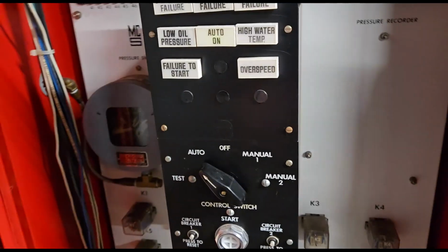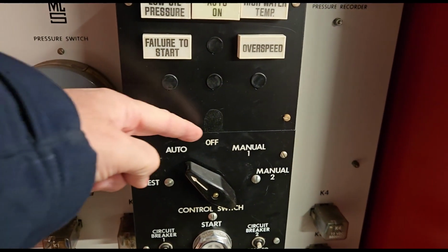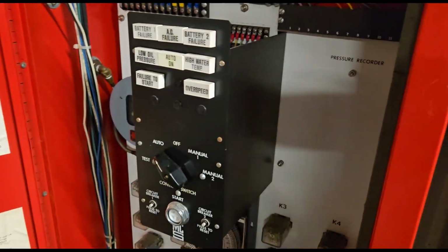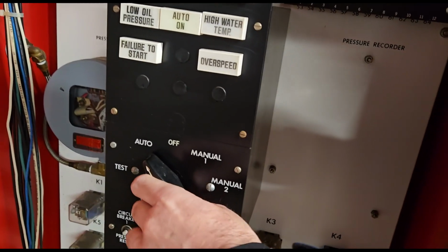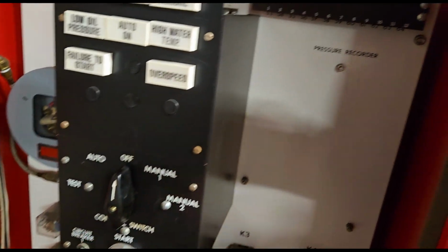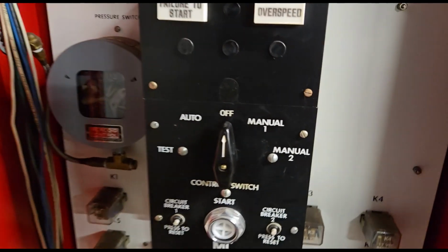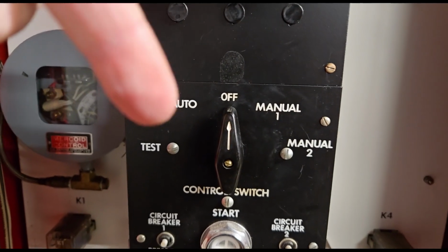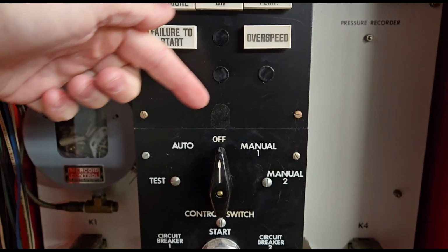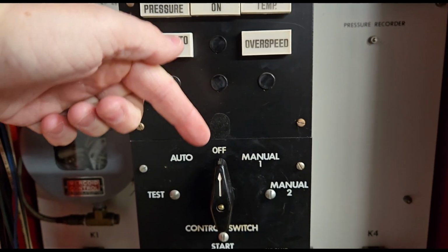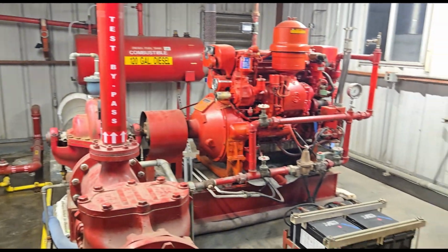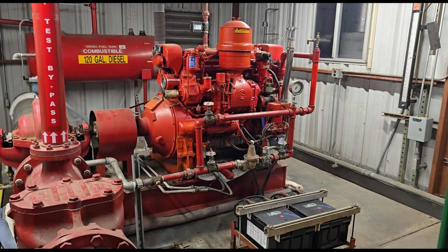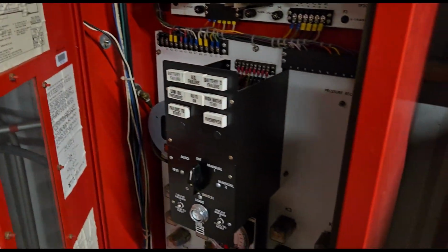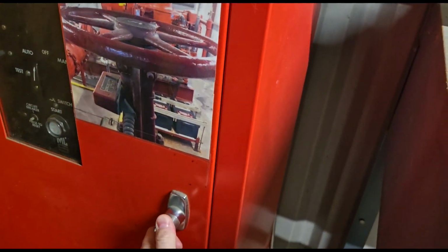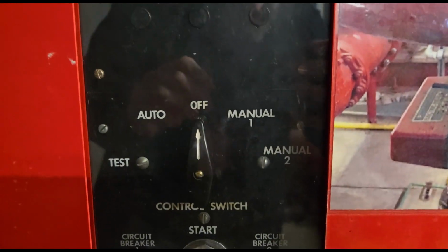So we're going to go ahead and just turn this dial from auto to off. Again, I'm going to stand off to the side, tilt my camera over, and we're just going to go like that to off. So now you see it was first on auto, now it's on off. So now the pump is off. This fire pump will not turn on for our flow testing. So we're just going to close up our door, lock it, so they can see it's on off.